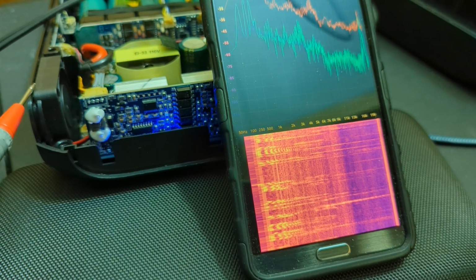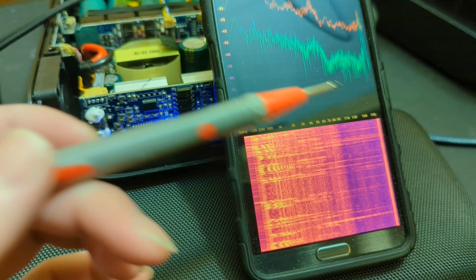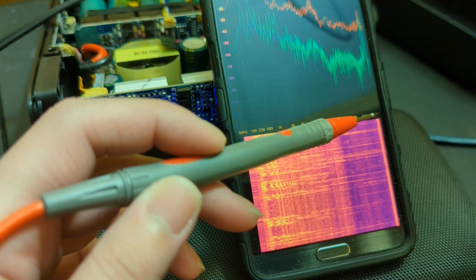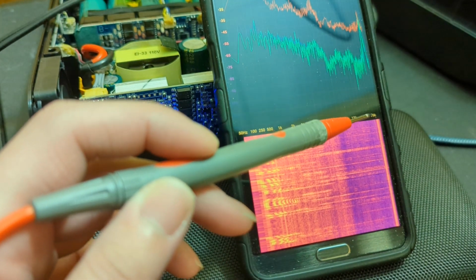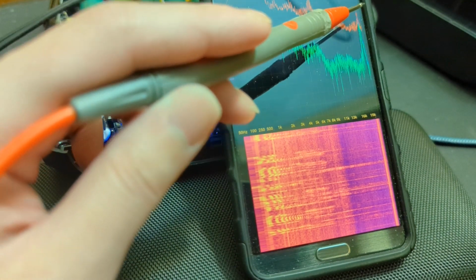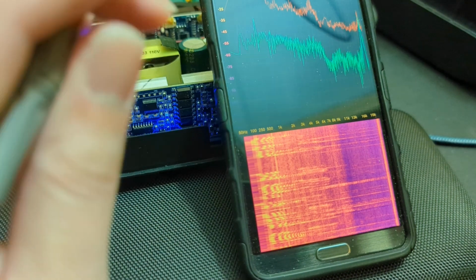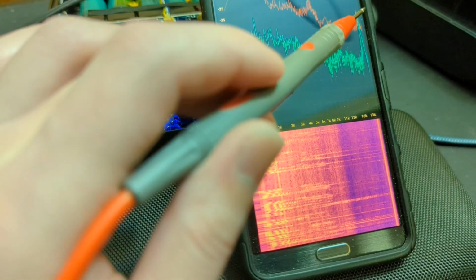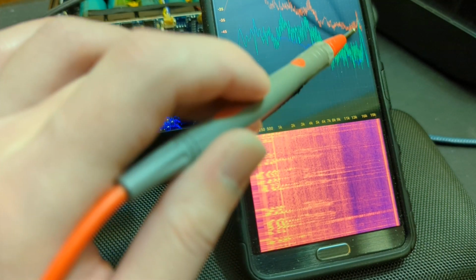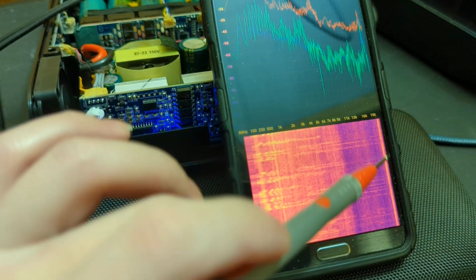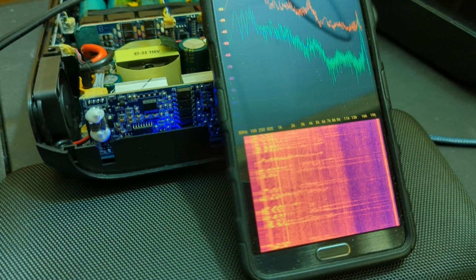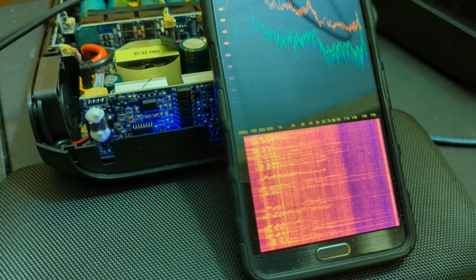It is this bright white line here at 19K, that is the high frequency noise coming from the inverter through the high frequency switching. This peak becomes much higher, and that white line is much brighter compared to when the inverter is on idle.